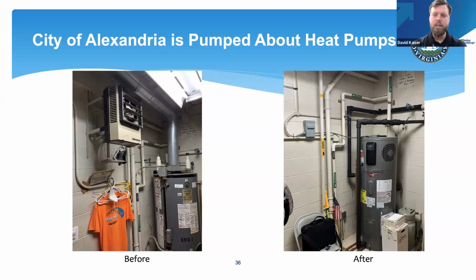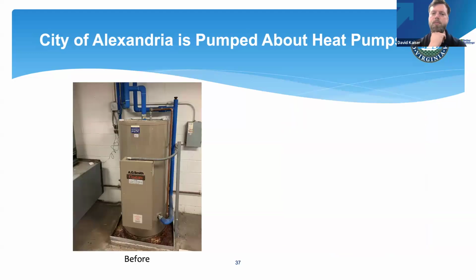So this is really only used for kitchen and hand washing, so it's very easy to downsize after measuring the amount of hot water that was used. In the previous example, we started with an 80 gallon and we were able to then use a 40 gallon heat pump hot water heater. So that was a good example. One of the other things I'll notice about these slides as I go through is that there's a lot of hot water heater changeouts, and the reason for that is that water heaters last the least amount of time of all the mechanical systems. So they change over a lot more, and so it's a lot easier to dig into those quicker. Next, please. Again, this is another heat pump hot water heater situation.